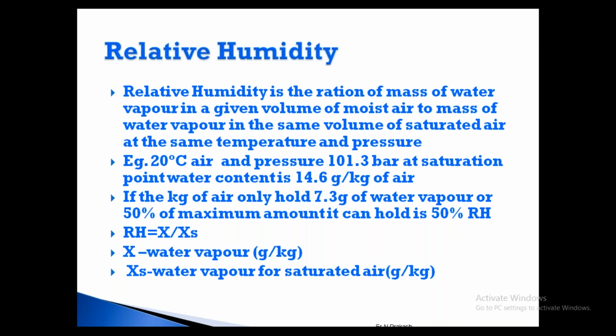Same air, when it is at 50%, if the kg is holding 7.3 grams, it is 50% RH only. At the same 20 degrees, it will be holding 50% of the moisture. That means only 7.3 grams of water vapor is evaporated in the air. That means grams per kg is less at 50% and more at 100%. Basically, it's water vapor. What is the amount of water vapor available in the air? That is only relative humidity. That only reacts with the hygroscopic nature of your material, which is basically cotton, mostly cotton.